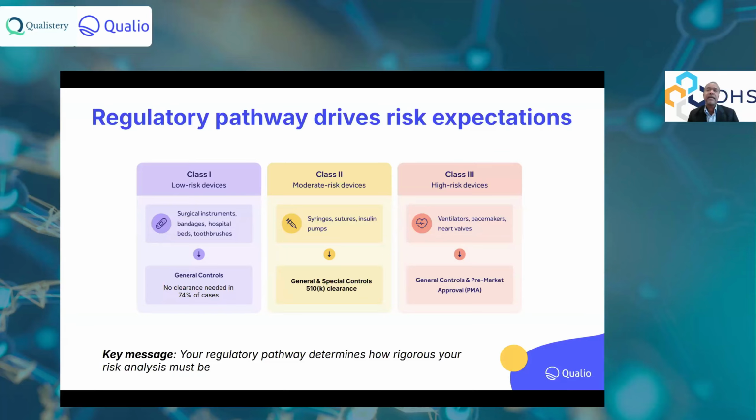If you find them and they are registered with FDA or they got clearance with FDA, you'd be able to see with their K number on the FDA website what codes apply to them. And perhaps all of those codes or some of those codes apply to you, right? So when you submit, you identify your codes, your predicate devices, your indications for use, and so on. And you're all set, parking it as a low-risk device or a moderate-risk device.